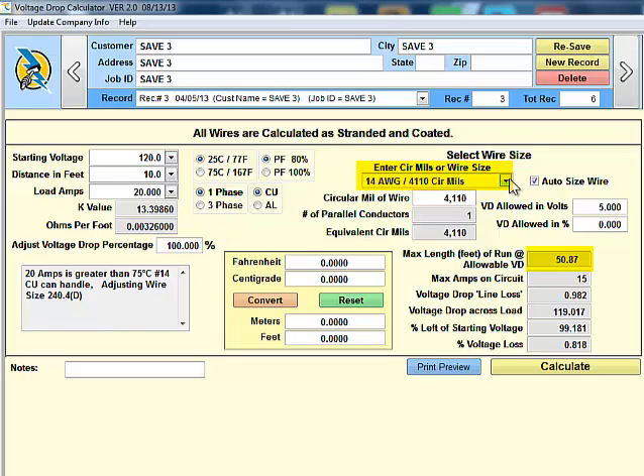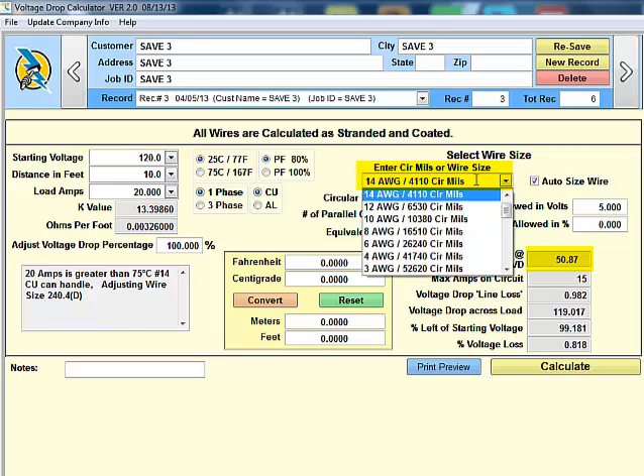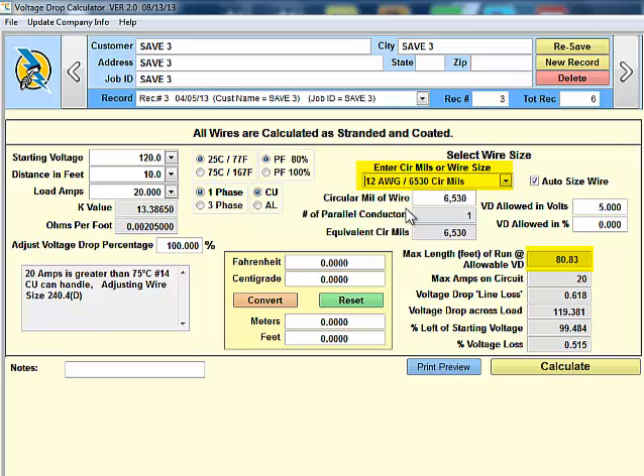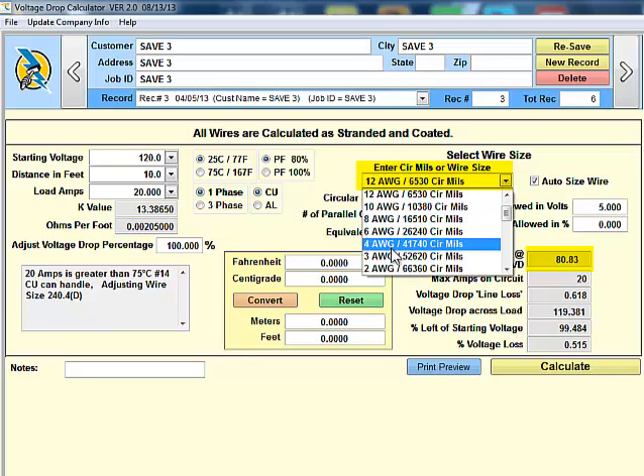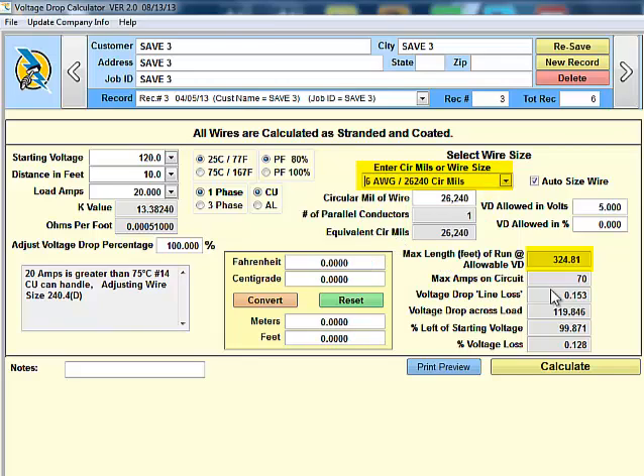If we increase the wire to 12, now we see we can go to 80 feet to maintain the 5 volt drop. Continuing, if we go to 6 American wire gauge copper, now we can go to 325 feet to maintain the 5 volts.